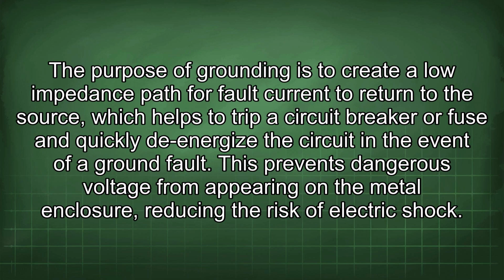The purpose of grounding is to create a low impedance path for fault current to return to the source, which helps to trip a circuit breaker or fuse and quickly de-energize the circuit in the event of a ground fault. This prevents dangerous voltage from appearing on the metal enclosure, reducing the risk of electric shock.